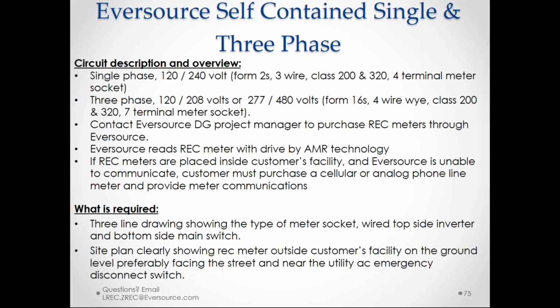So again, different types of meters. There's self-contained, single-phase and three-phase meters. Single-phase 120/240 volts, Form 2S, 3-wire. We can issue those as Class 200 or Class 320 meters, and those are 4-terminal self-contained sockets. The three-phase can be 120/208 or 277/480. So those are typically the Form 16S socket, 4-wire. Class 200 or Class 320 is a 7-terminal socket.